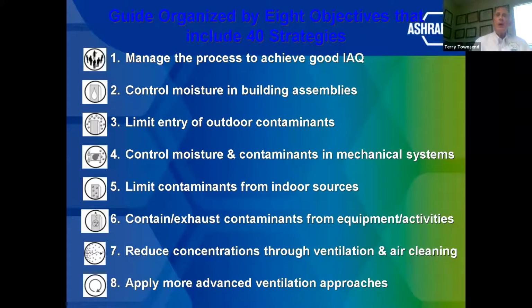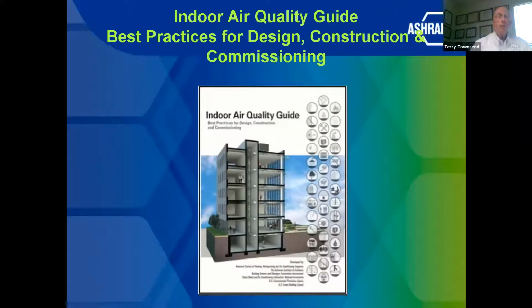Now, however, what I would suggest that you do, especially on this indoor air quality guide, I would buy a hard copy of it. And the reason for that is that with the hard copy of the IAQ guide, you get a CD. And the CD has over 500 additional pages of material for check sheets, for commissioning, guidelines, as well as design guidance sheets that you can utilize, sequences of operation, etc., as a design engineer. It doesn't come with a download. It only comes if you buy a hard copy of it.